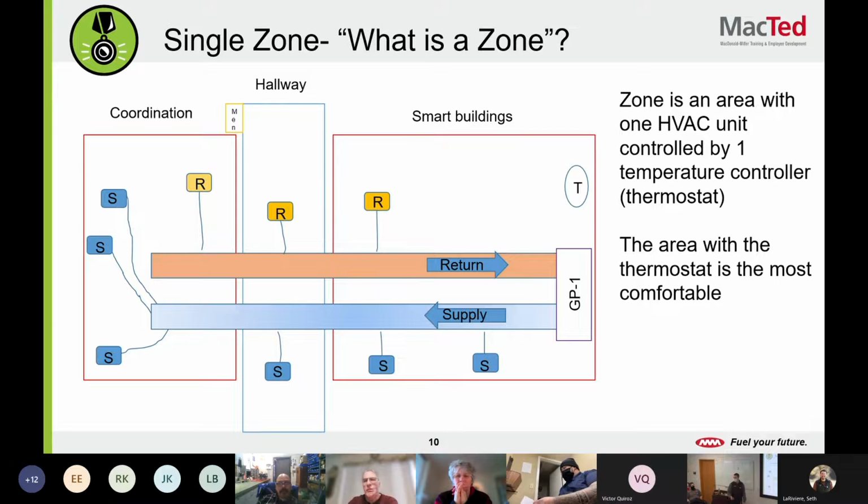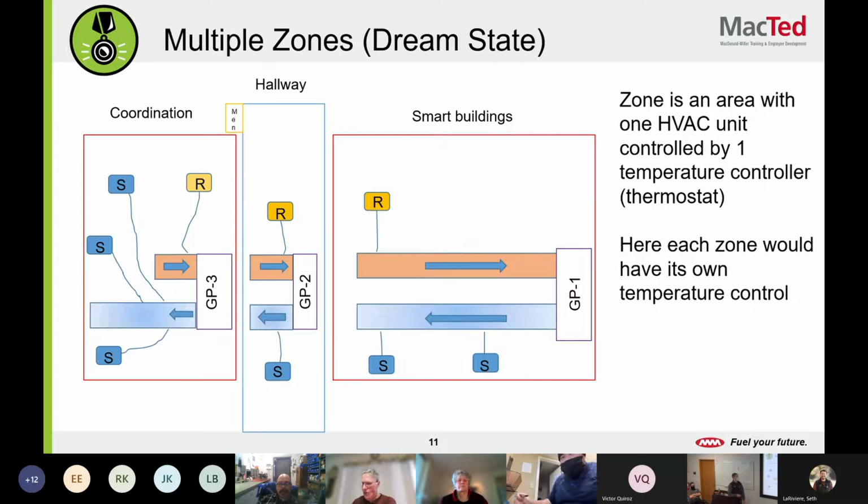That's a really common one, especially for office spaces where you'll have one unit that serves multiple, and especially when you do a TI project and now you subdivide offices, or they don't add a supply grill to another one. You'll end up running into those issues.